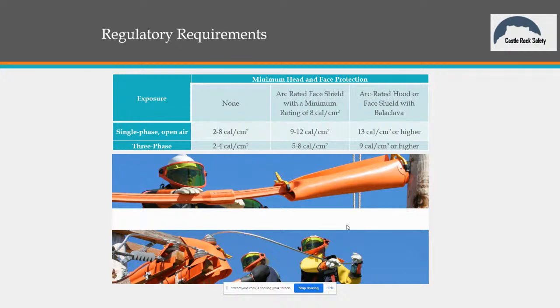So they determined they were going to cut us a little slack on face shields. They also determined that the face, even if I got third-degree burns on my face, if the rest of my body was protected with arc flash clothing, I would survive that. What they're trying to do is make everything survivable. You read some of this in the preamble, and they're basically saying, you might have to sacrifice your face.